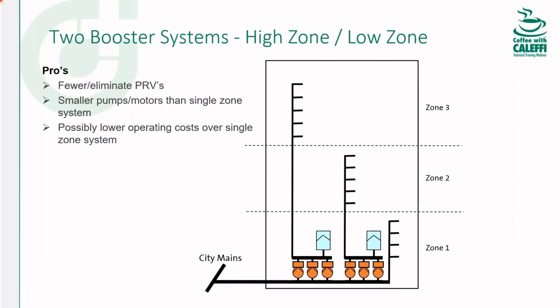By doing it this way, you can reduce the number of pressure regulator valves. You can also get your pump sizes to be smaller. That will actually improve your pumping efficiency a little bit, because if nobody's using water in the high zone and then somebody's using water in the low zone, well, your high zone pumps are off. Remember, you put the bladder tank down there, so it's stopping at low flow. And then maybe your low zone is the only one that's operating. So you're splitting up the water distribution to the building this way. So you can reduce operating costs, and you can reduce the number of pressure regulator valves, which does offset costs.